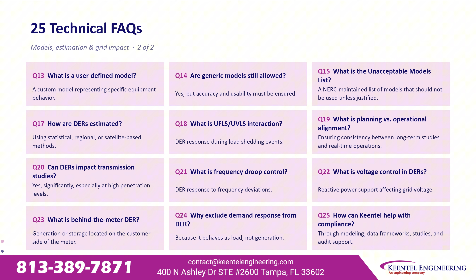Rooftop solar, behind-the-meter batteries, distributed generation. For years, the grid treated them as invisible load offsets. Under NERC's updated MOD-032-2 and FERC Order 901, that's no longer acceptable. Distribution providers and transmission owners must now model DER location, capacity, and dynamic behavior, even estimating data when it isn't available, with full documentation. Inverter-based resources face the same scrutiny. Ride-through, tripping behavior, frequency response, all required.